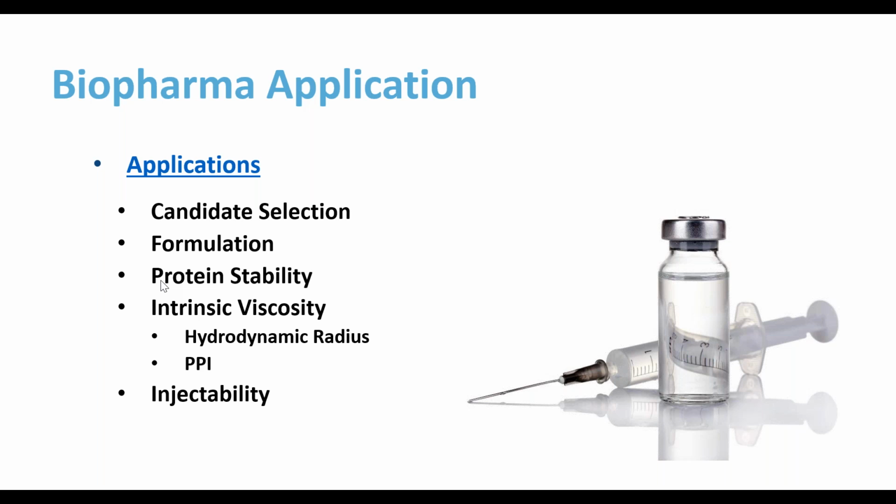Also with our technology, you have the ability to reach high shear rates. And with high shear rates, you can use that for injectability studies. You could use that to do calculations on injection forces. There are ways to also mimic the shear at the needle with this high shear capability.